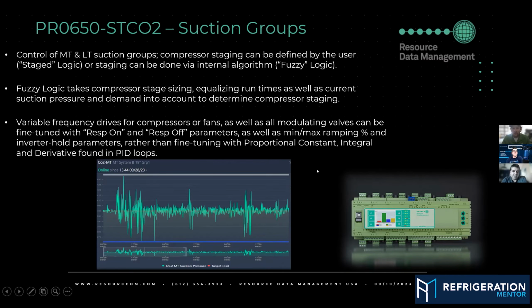And then in some of these settings in the controller, both for suction groups, the gas cooler group, receiver control, as well as our case controllers, you have these fairly ubiquitous set points called response on, response off. And then you have inverter min, max, ramp as well as inverter hold. These are all settings that are really useful if you see your suction pressure or your discharge pressure or a valve opening too fast or too slow. You can dial these numbers in.